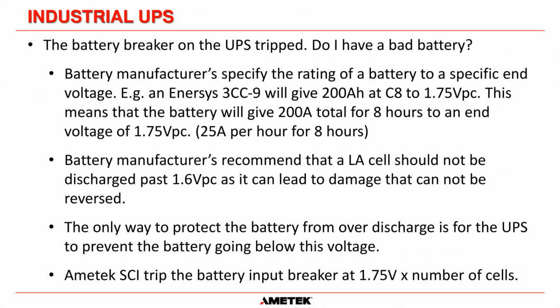Another misconception we hear quite frequently is: the battery breaker on the UPS is tripped, do I have a bad battery? You have to understand that the majority of UPS manufacturers have a battery disconnect level to protect the batteries from over discharge. This is specifically for lead acid batteries more than anything, because battery manufacturers specify the rating of the battery to a specific end voltage. I've used as an example here the Enersys 3CC-9, which is a wet cell lead acid battery.